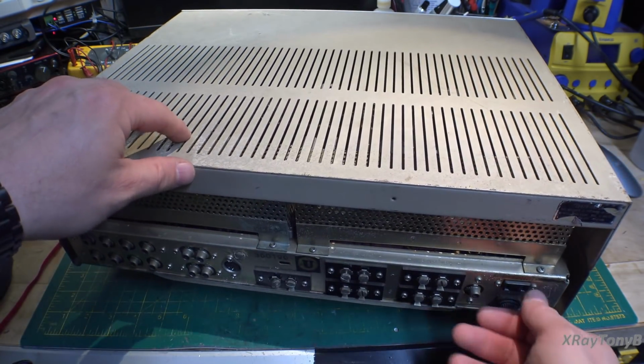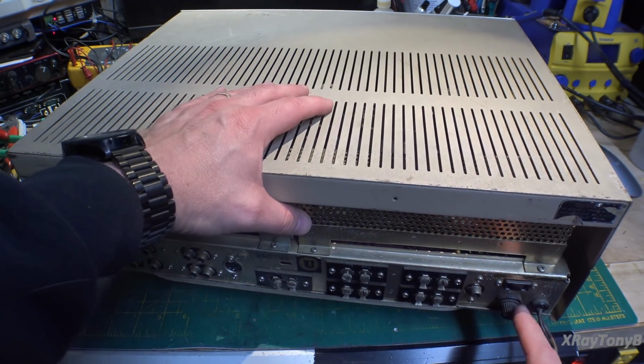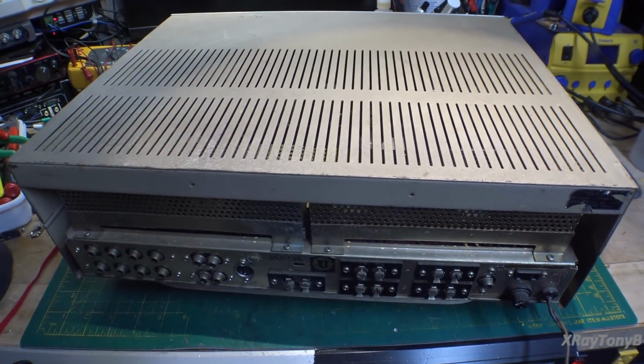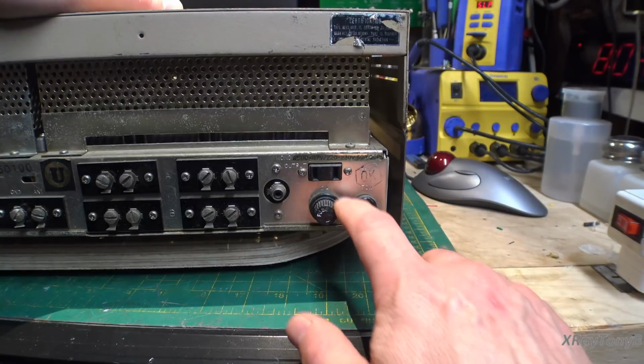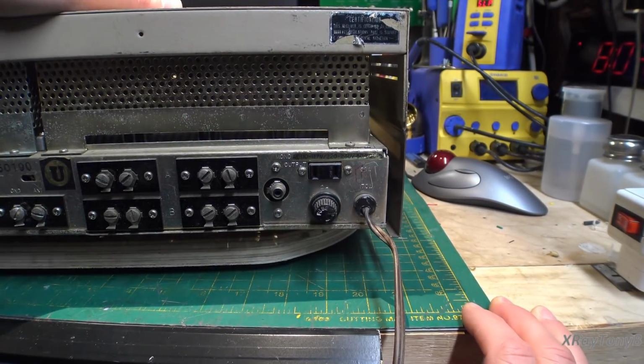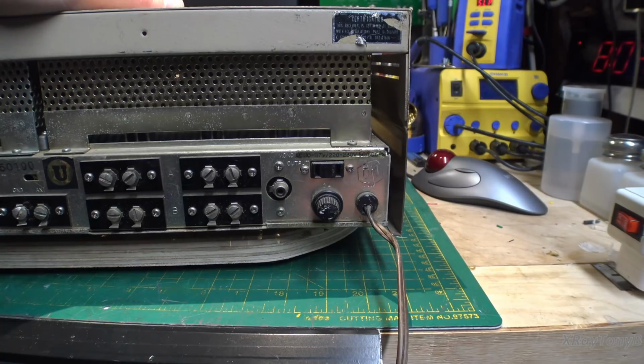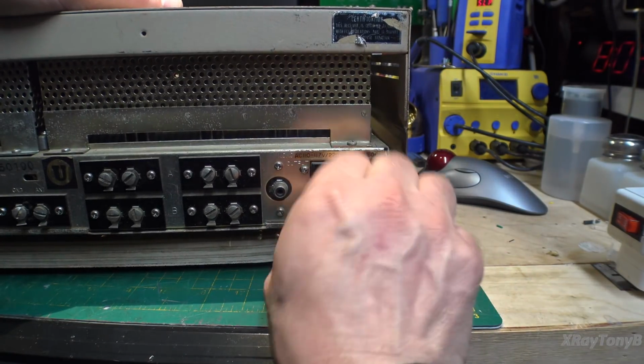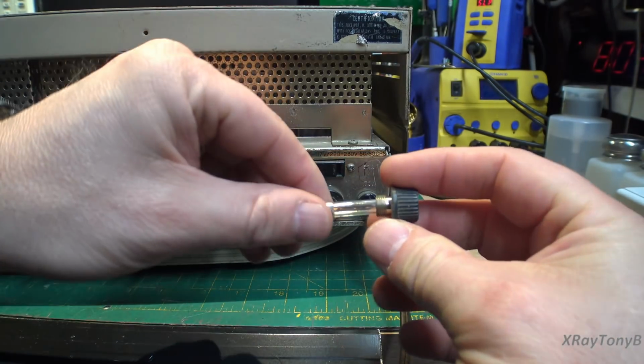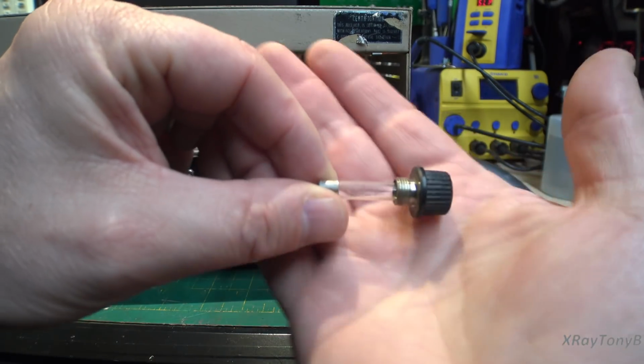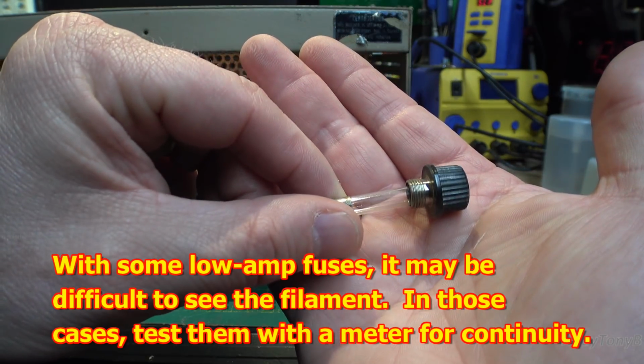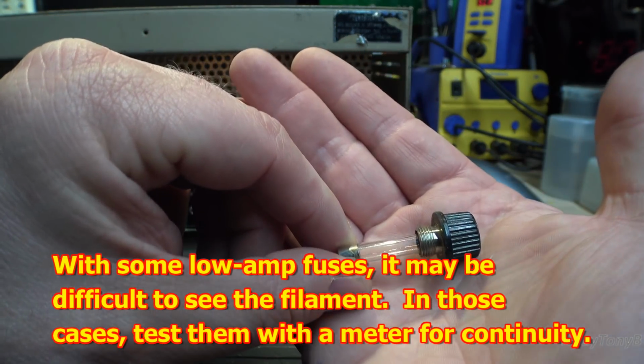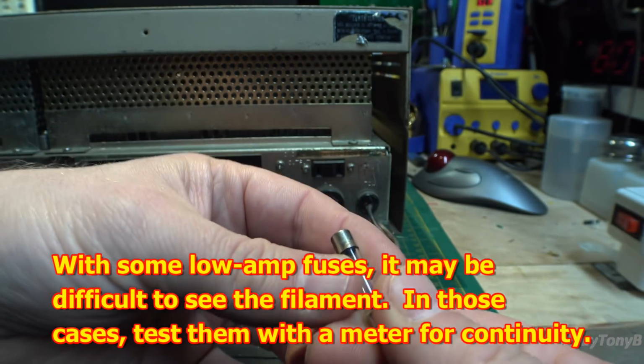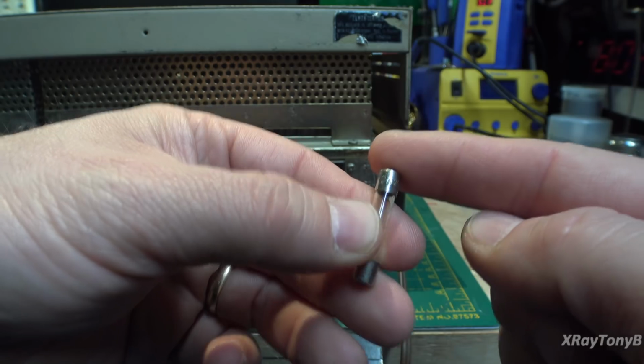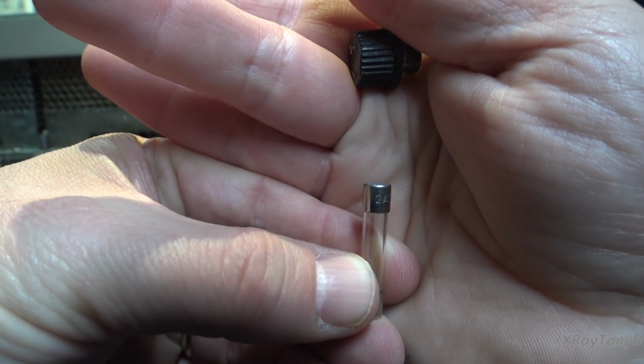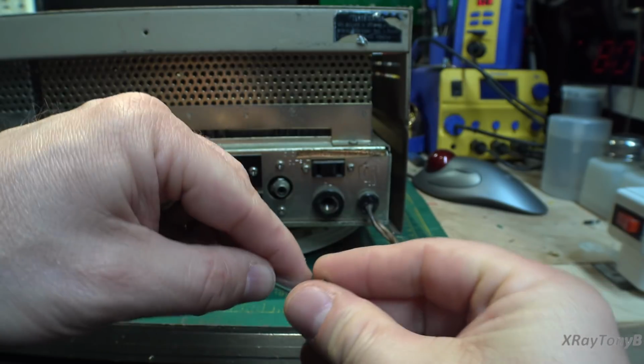The other thing I check is the fuse. You always want to check your fuse. Let me move the camera down. We look at the fuse and we can see on this one it says 2 amps, right? So we know that it's supposed to have a 2 amp fuse. I will remove the fuse and check it, and when we look up close, it does not appear to be blown. You can still see the filament in there, and if we look at the value, you can see it says 2 amps. So it has the correct fuse, and the fuse is good.